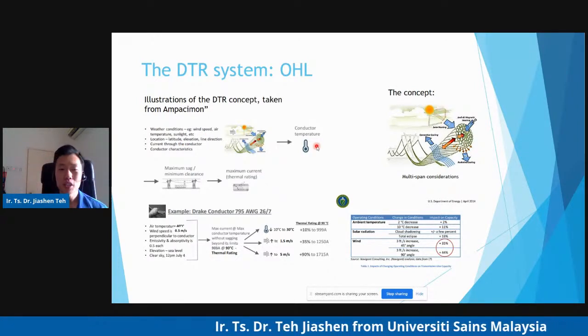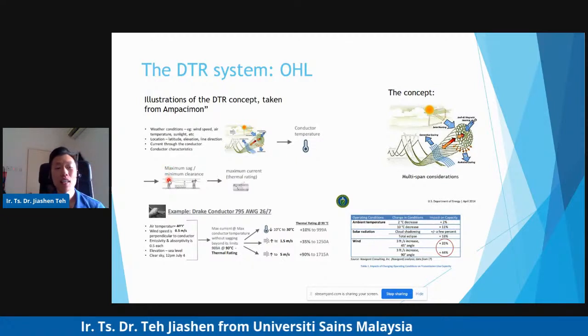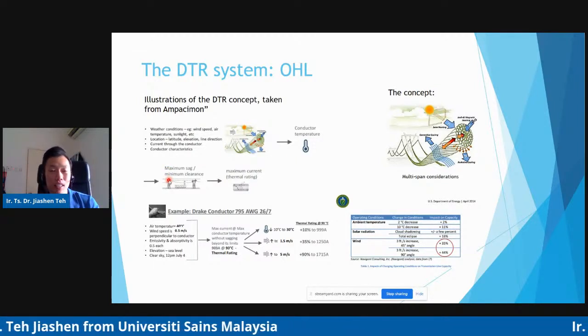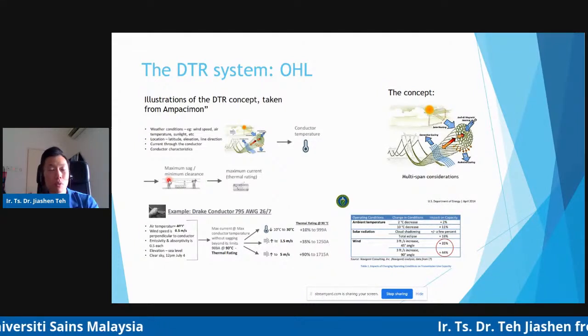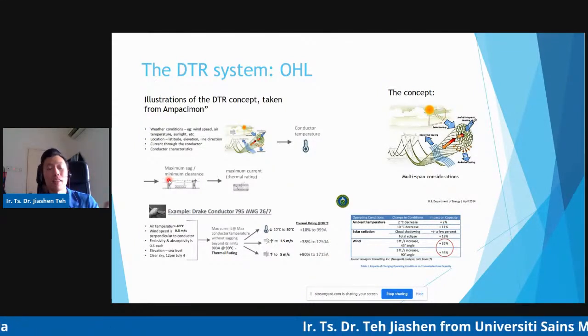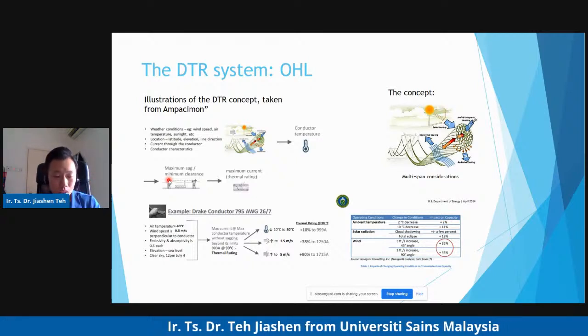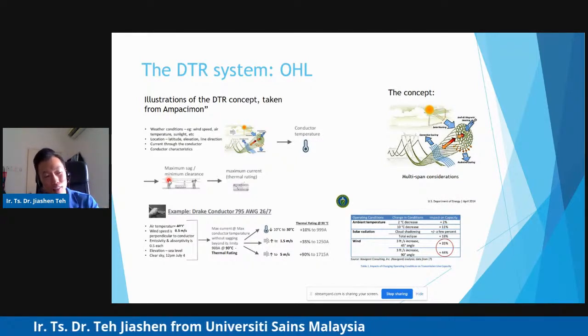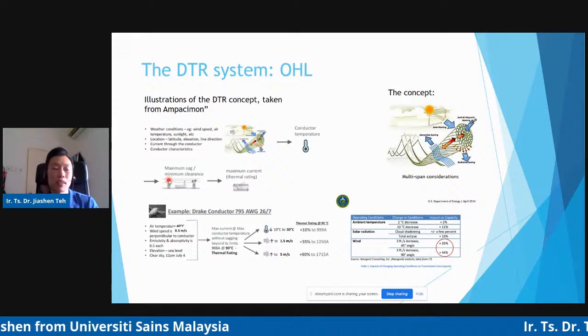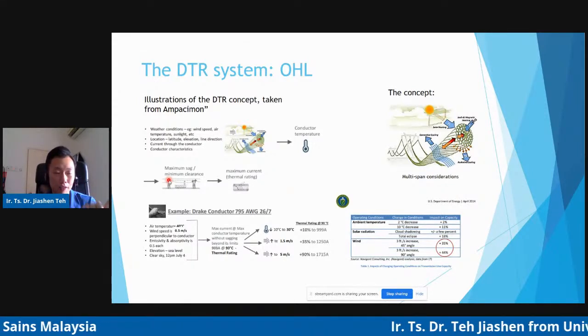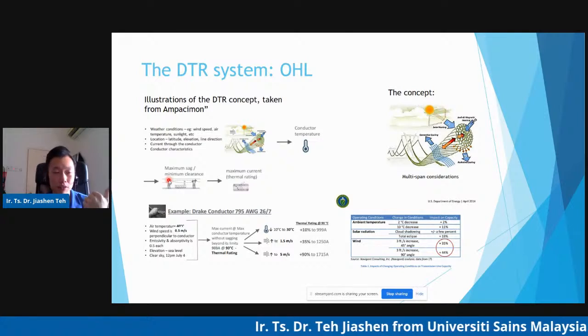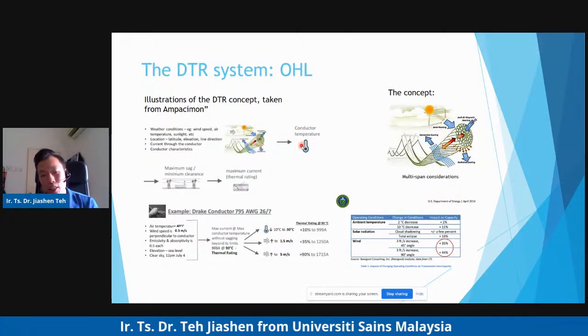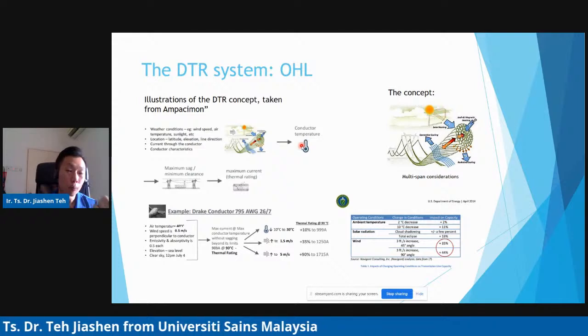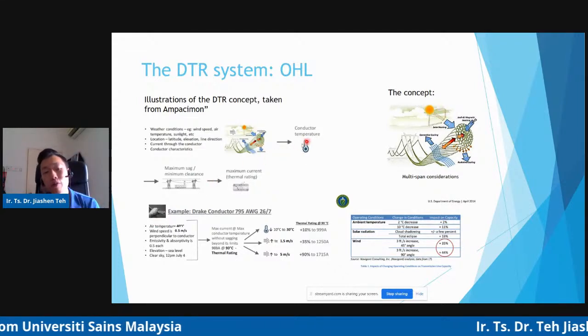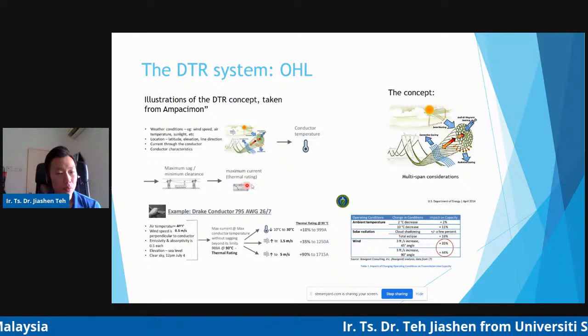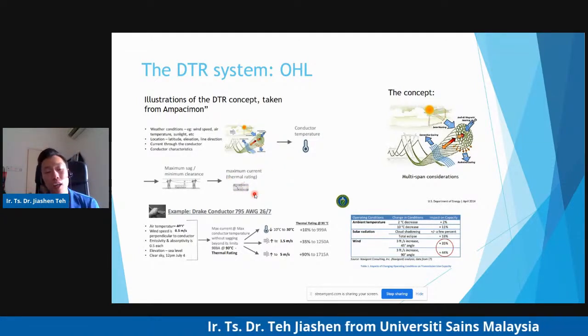As we know the conductor temperature, we can determine the sagging level of the conductor. As the conductor heats more, the steel will expand, and as it expands, it will sag. The maximum amount of sagging allowable is the safety limit enforced by the utility, from the regulation perspective, while conductor temperature limit is from the component safety limit. These two factors combine to determine the maximum rating of the conductor.